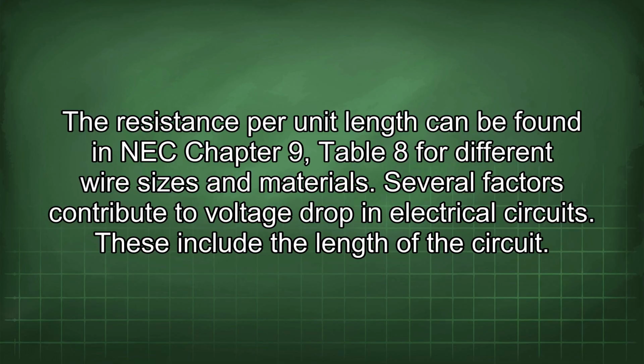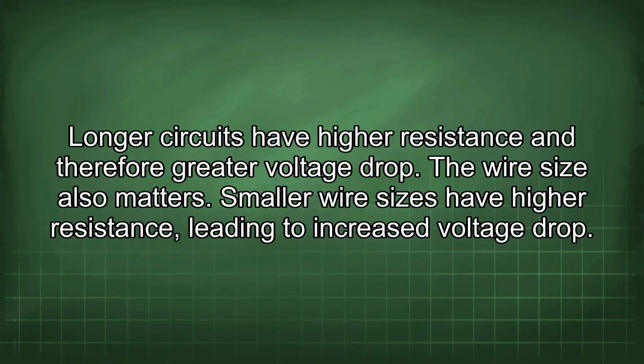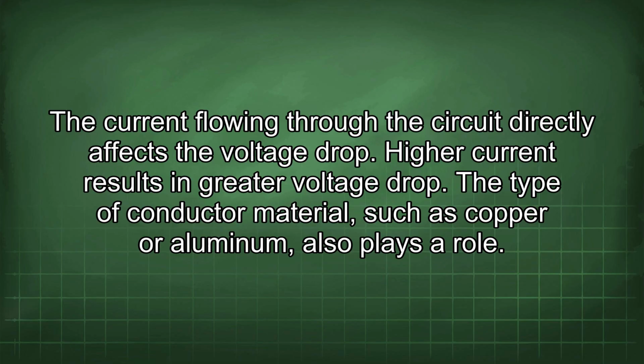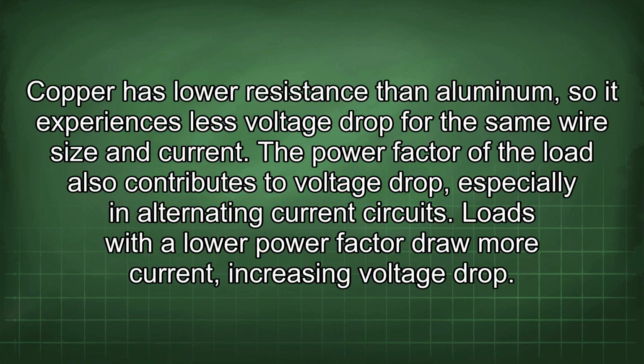Several factors contribute to voltage drop in electrical circuits. These include the length of the circuit. Longer circuits have higher resistance and therefore greater voltage drop. The wire size also matters. Smaller wire sizes have higher resistance, leading to increased voltage drop. The current flowing through the circuit directly affects the voltage drop. Higher current results in greater voltage drop. The type of conductor material, such as copper or aluminum, also plays a role. Copper has lower resistance than aluminum, so it experiences less voltage drop for the same wire size and current. The power factor of the load also contributes to voltage drop, especially in alternating current circuits. Loads with a lower power factor draw more current, increasing voltage drop.